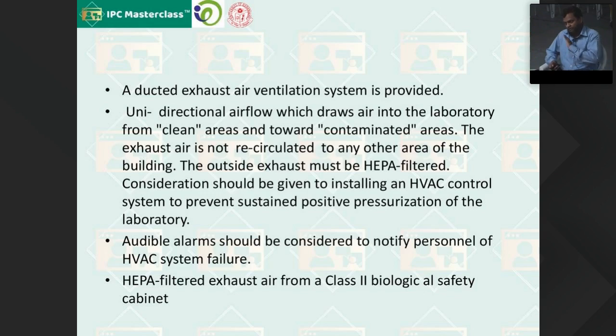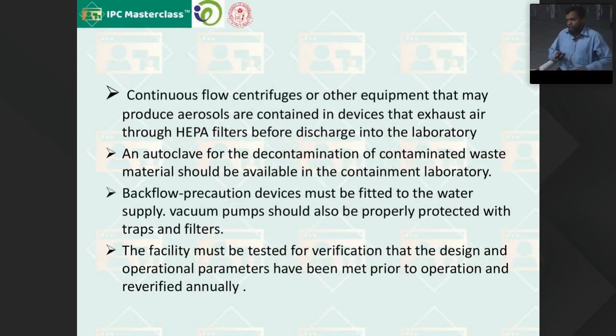So whatever is there in the BSL3 is, one, the unidirectional airflow. Second, the exhaust should not be recirculated. If it is being recirculated, it has to pass through the HEPA filters. And it is better if you can have an HVAC system, plus or minus, in the BSL3 lab, depending on the type of work we do. And all the exhaust air has to be HEPA filtered before it is dispersed into the outside environment. Okay, and also there should be a continuous flow. The equipment should not generate aerosols, because if it is being generated, then it should pass through the HEPA filters.